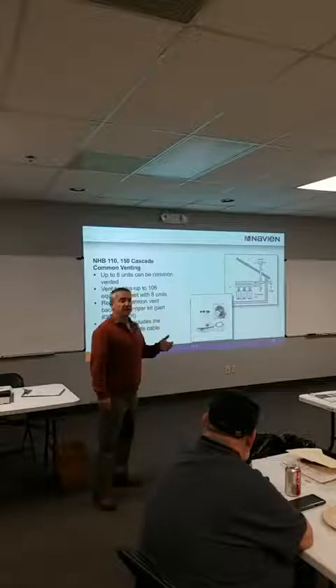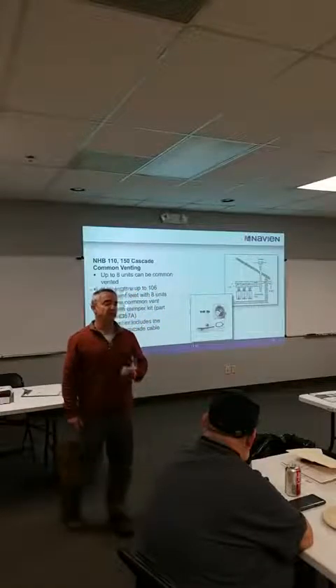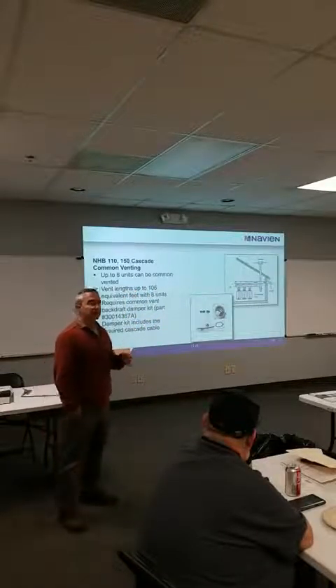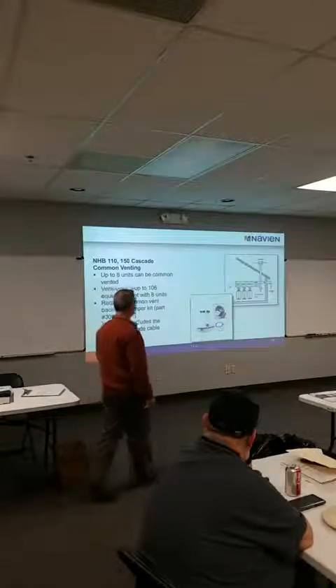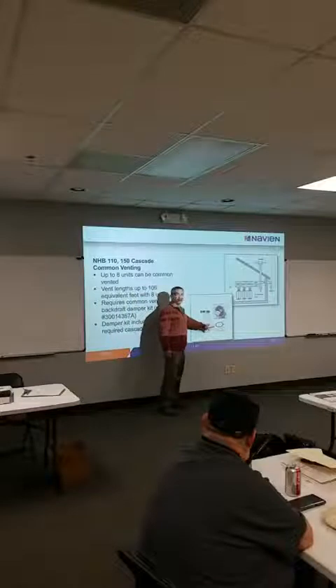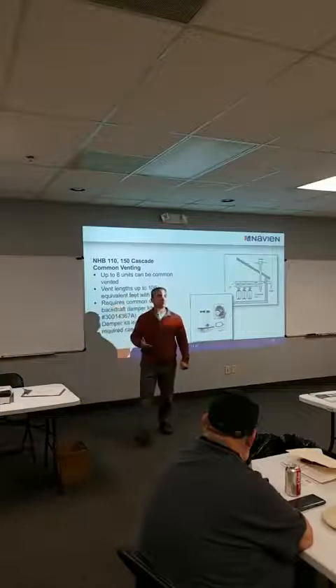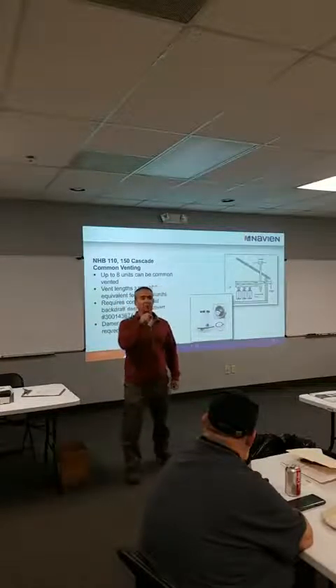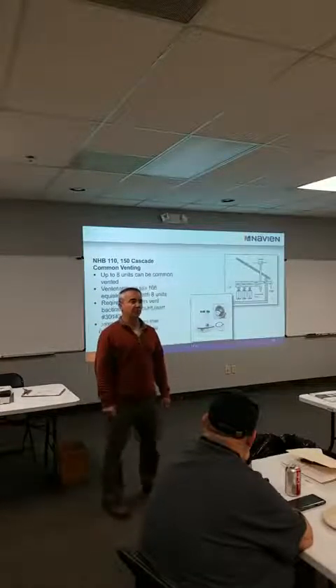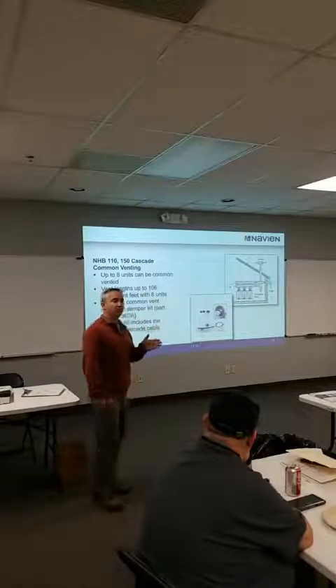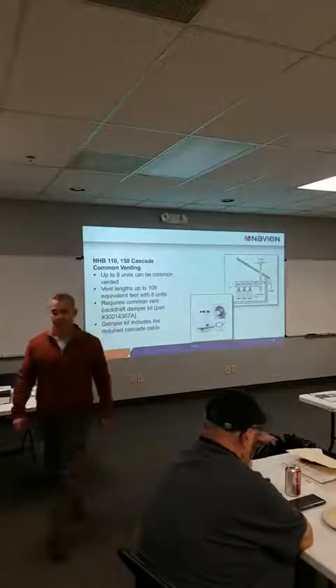That wasn't the case before we got our ASA or CSA approval. Once we got our CSA approval on all our equipment, they mandate that you have to have an exposed damper that has a visible port so you can make sure that it's operating properly. We put a damper in all of our units, but there's no port on it to look at it. It's actually between our fan and our burner assembly. And that's the same with all the units.